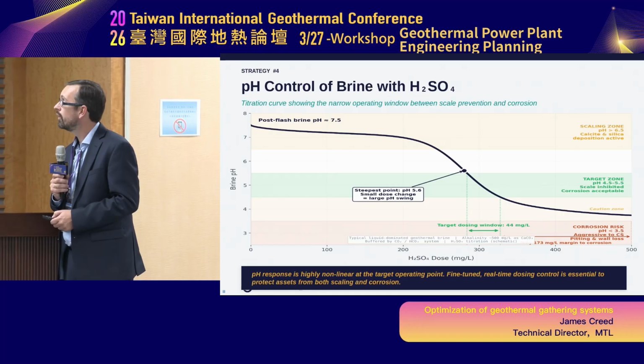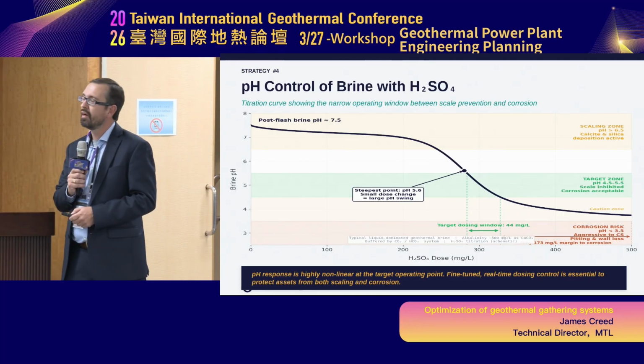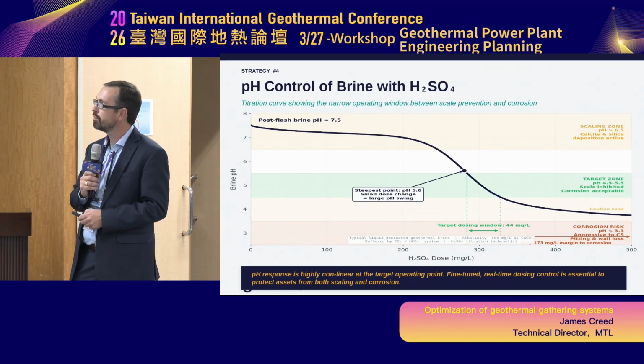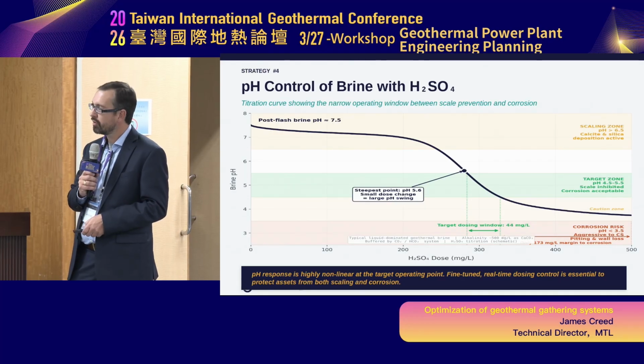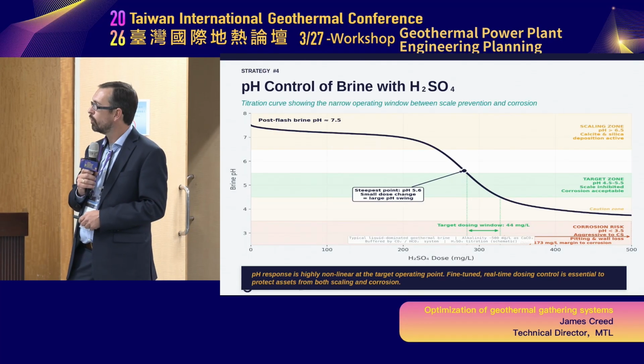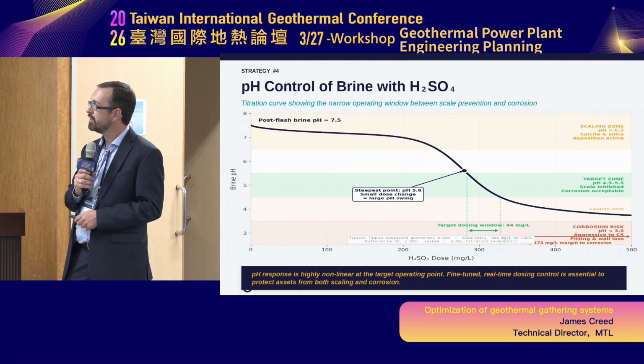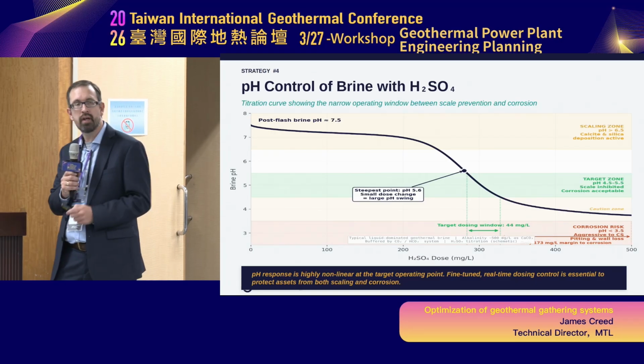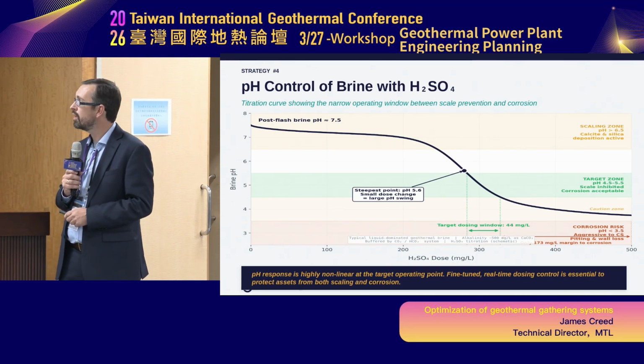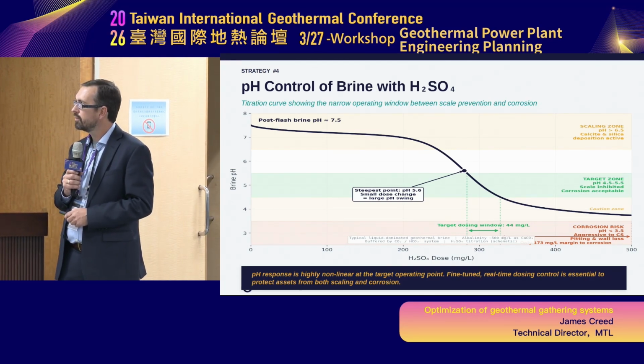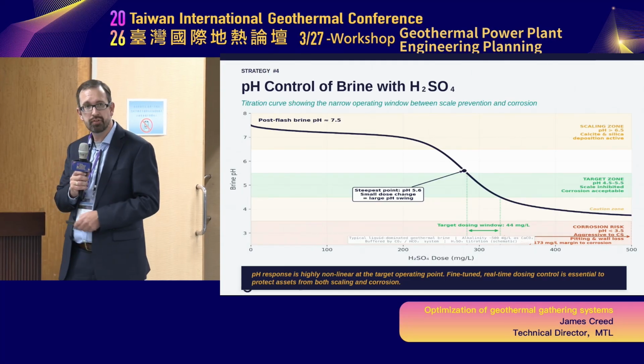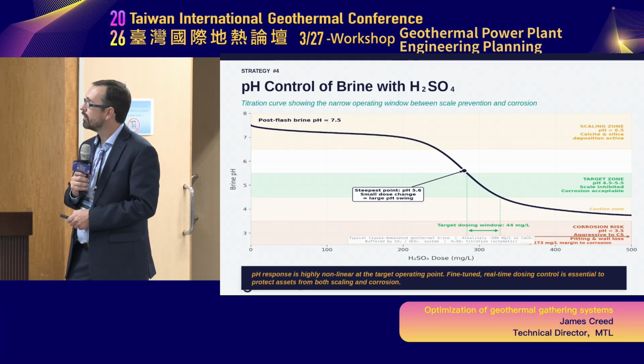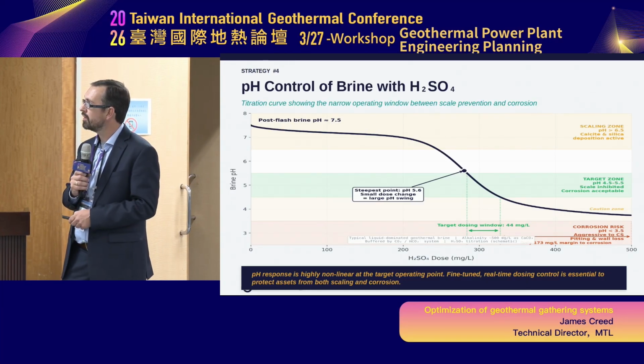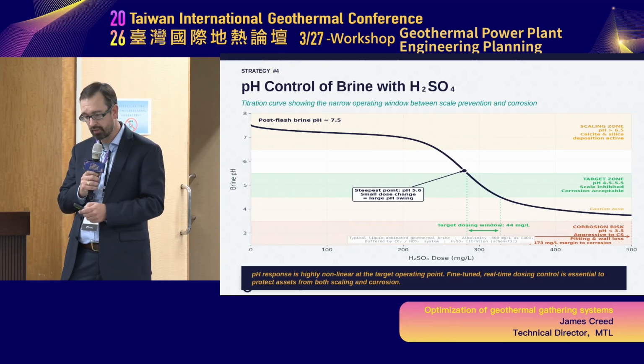In terms of pH control of brine, you're trying to control a titration curve within a very short band. If you change the amount of acid being injected, you slide up and down this curve very quickly. Slide too low and you get corrosion problems; don't put enough acid in and you'll be unsuccessful controlling silica dropout. Having the skills and understanding to manage this is key to your project's success.